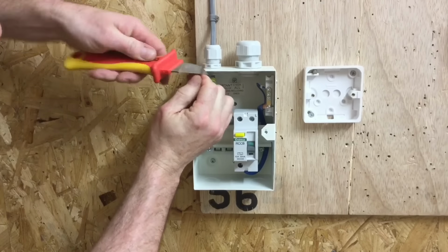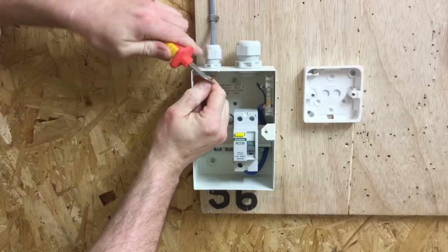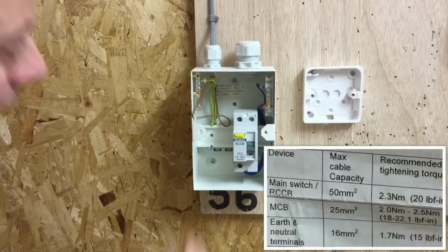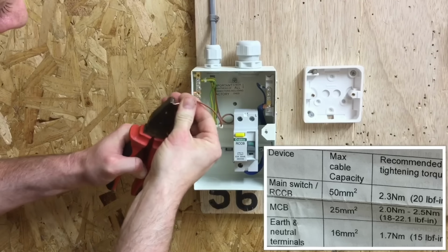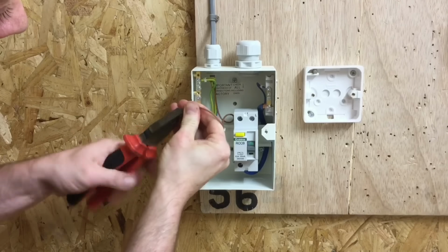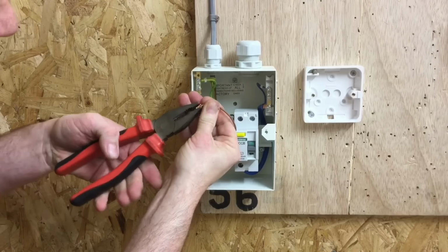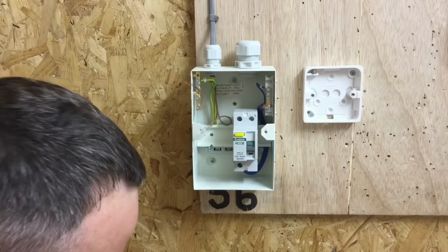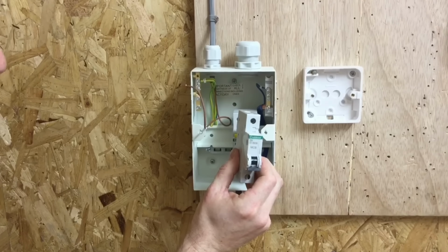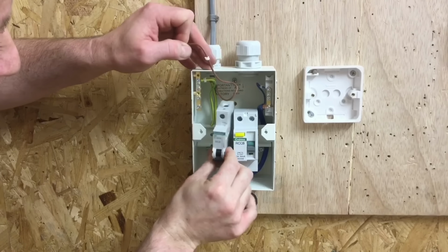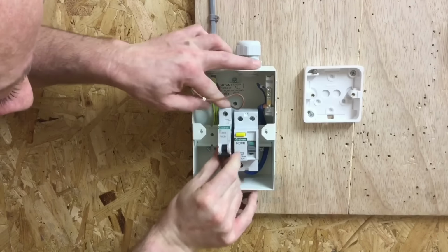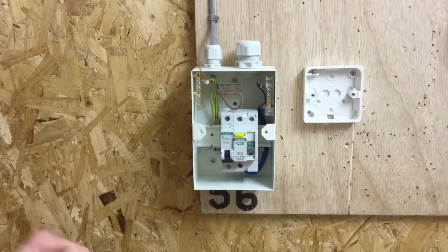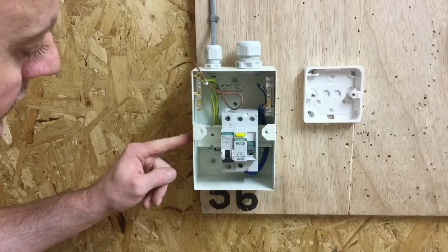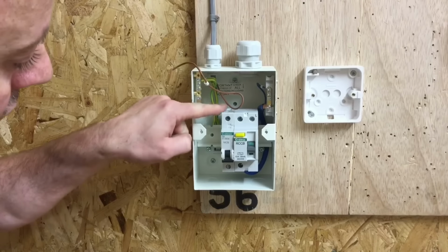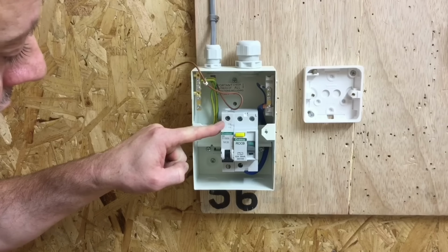This time the Newton meters of torque for the circuit breaker is different to that of the neutral and earth bar, and I've set my torque screwdriver to 2.3 Newton meters of torque. Double my termination over as we always do. Take my 6 amp type B circuit breaker for a domestic dwelling. I'm going to pop it into position onto the DIN rail, and hopefully it finds and locates itself into position, and that's ready for the final termination of the line conductor into the top of the circuit breaker, and then tightening up with a torque screwdriver.